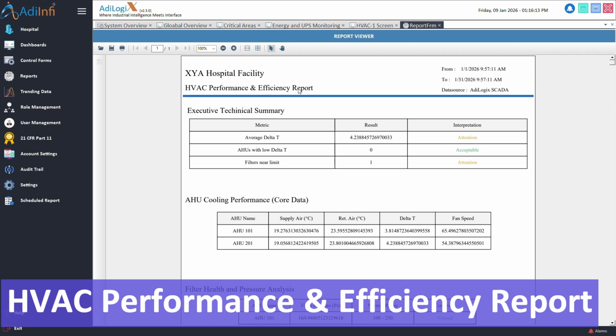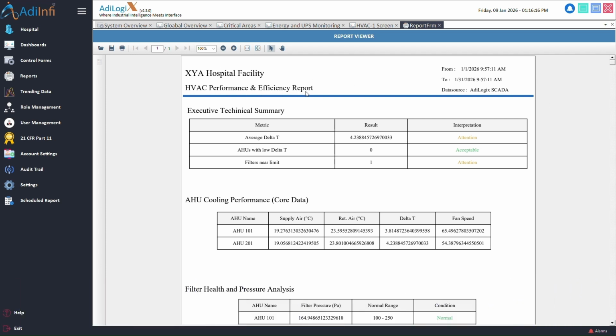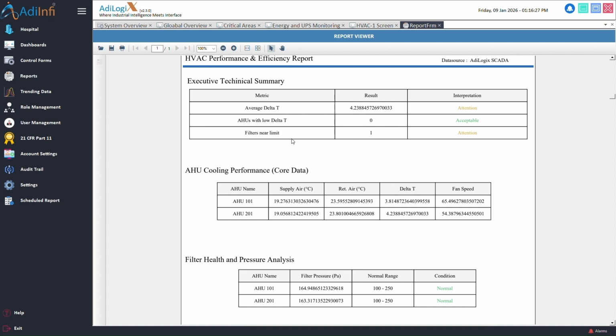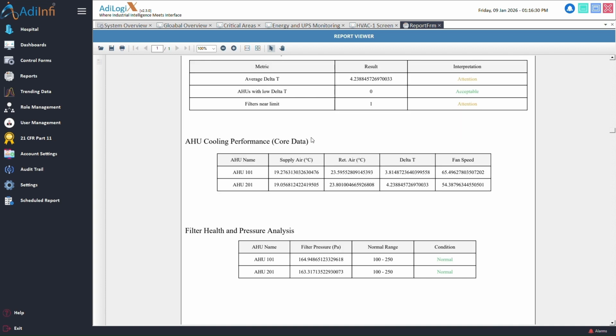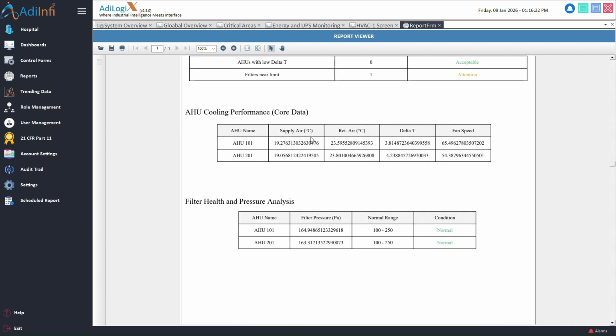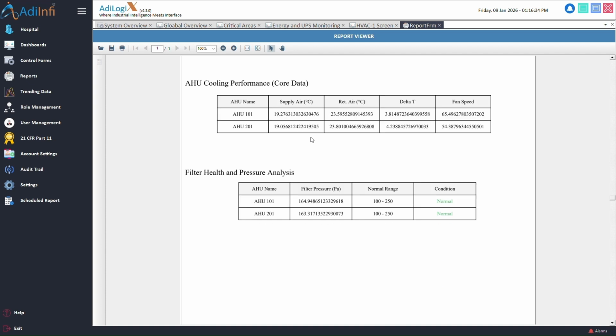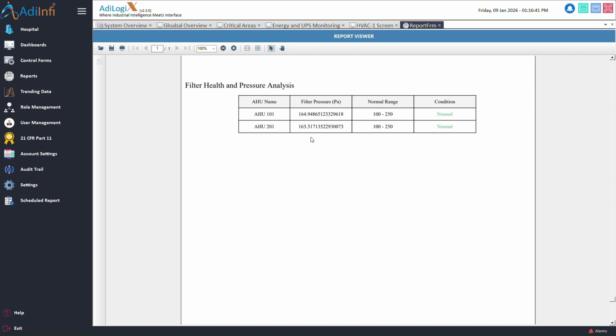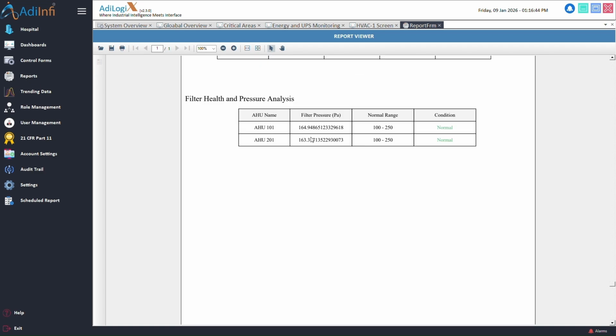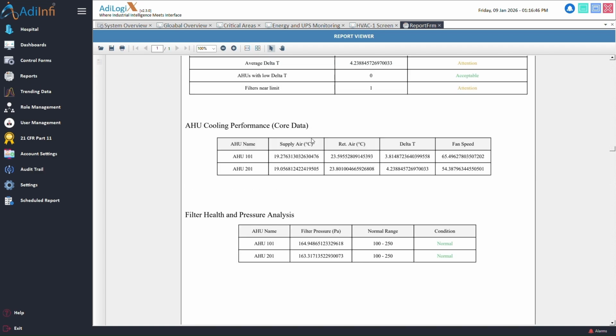The HVAC Performance and Efficiency Report focuses on the systems that drive the hospital's largest energy spend. Key metrics include delta T, return minus supply, fan speed versus valve position, and filter pressure trends. Our analytics highlight AHUs with poor heat exchange or high fan duty, the exact symptoms of coil fouling or control issues, and prioritize preventive maintenance opportunities. Proactive HVAC interventions conserve energy, improve patient comfort, and reduce unplanned downtime.